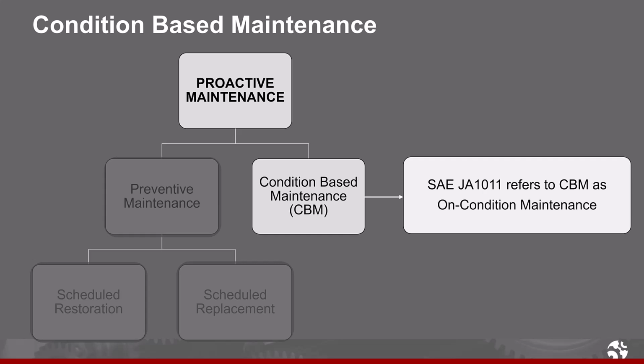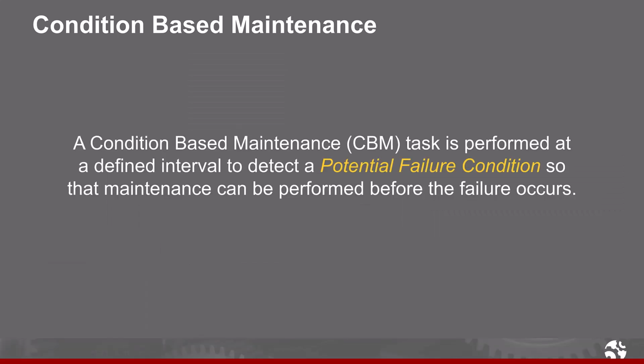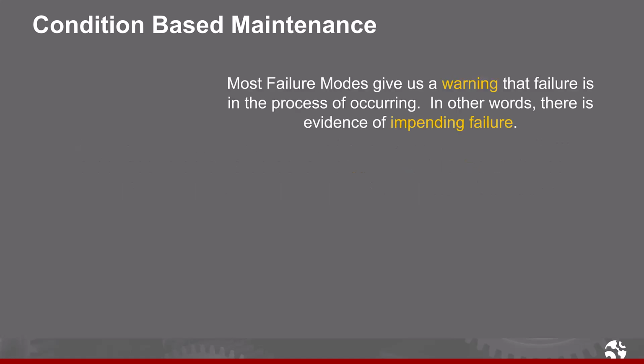Condition-based maintenance, or CBM, is also referred to as on-condition maintenance. These two terms are used synonymously. A condition-based maintenance task is performed at a defined interval to detect a potential failure condition so that maintenance can be performed before the failure occurs.